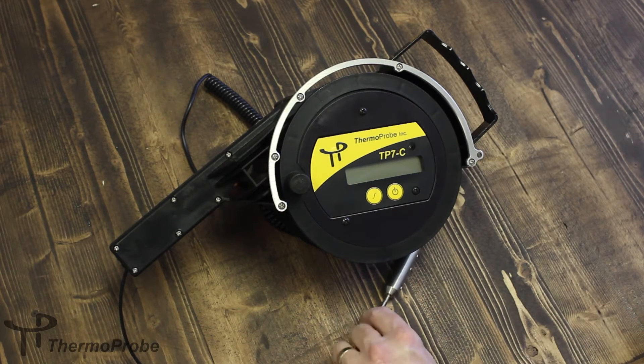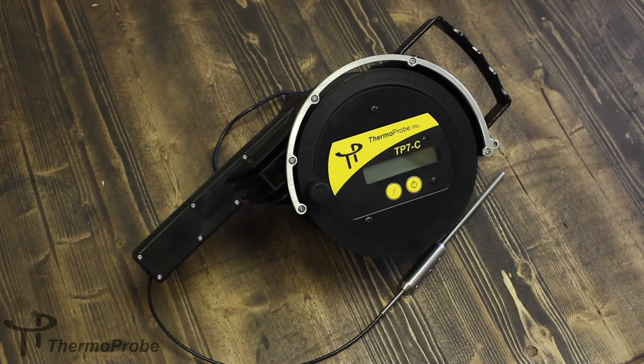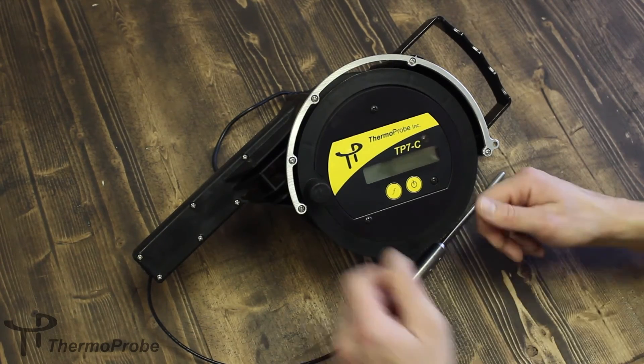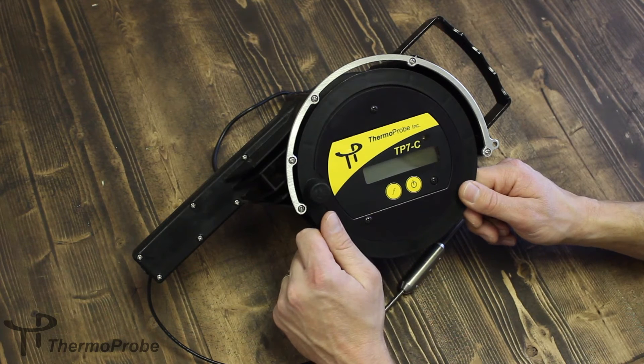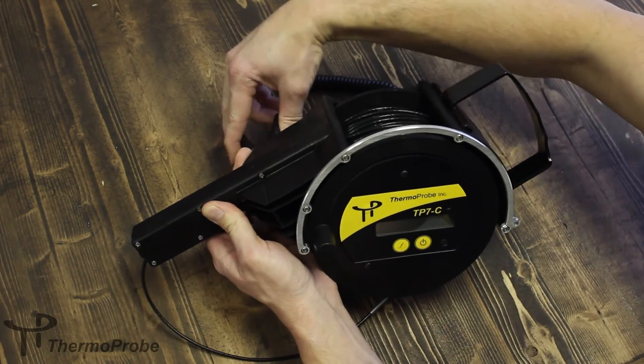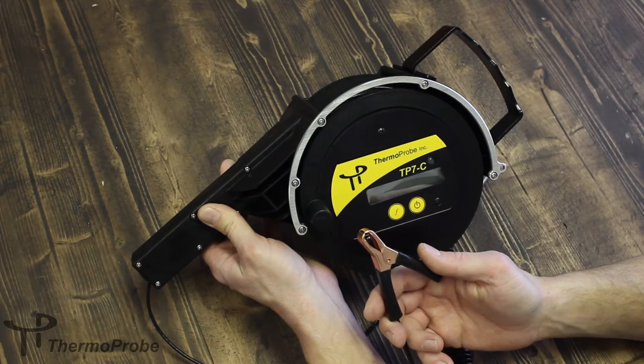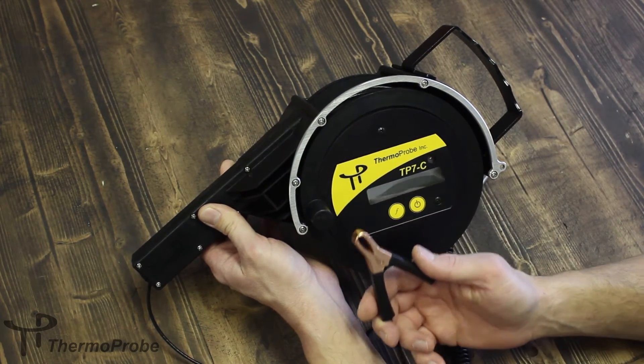The cable itself uses a non-stick insulation that allows for quick cleaning in the field. The TP7C is constructed from a rugged, static-dissipative plastic which prevents accumulation of static in hazardous locations. This static is dissipated through a ground connection that is connected to earth while the instrument is being used in the field.